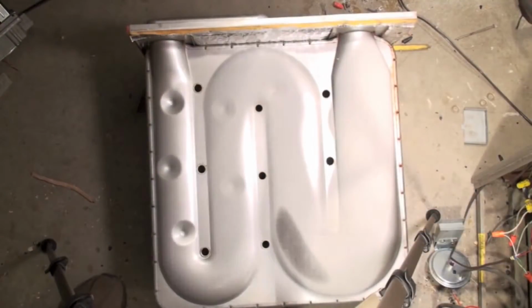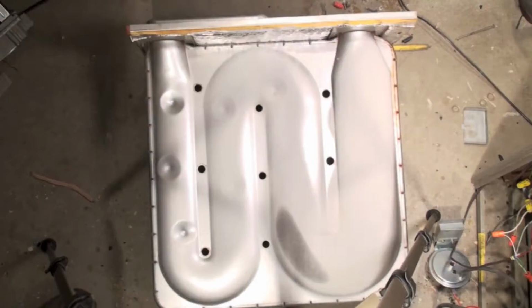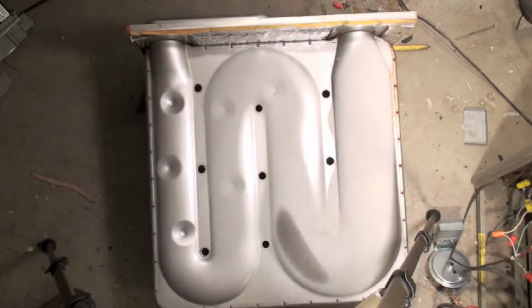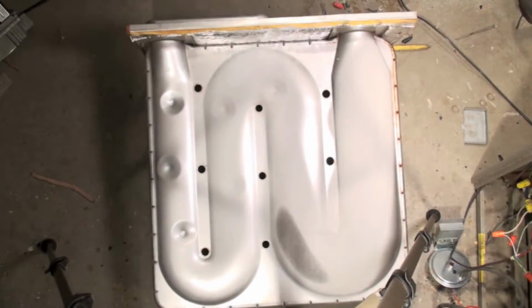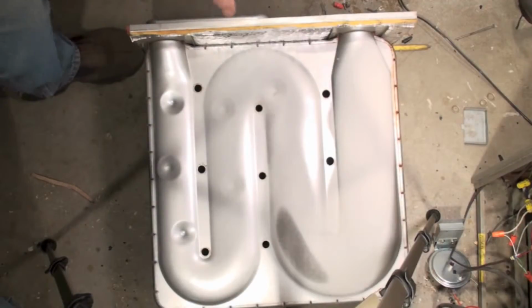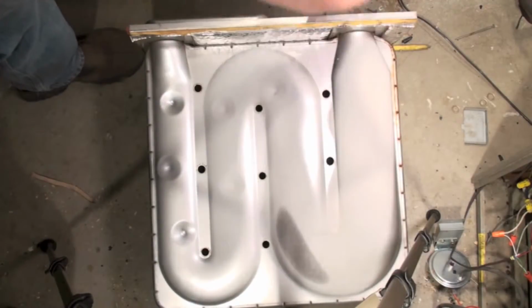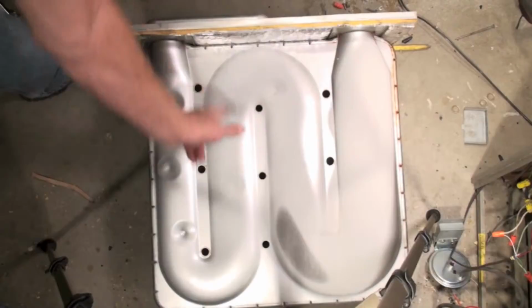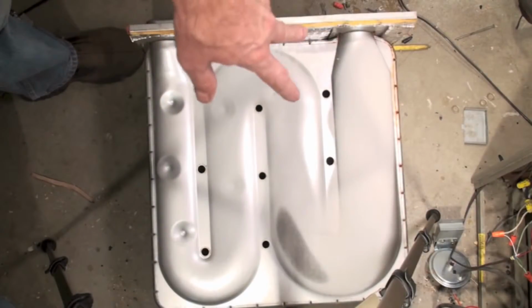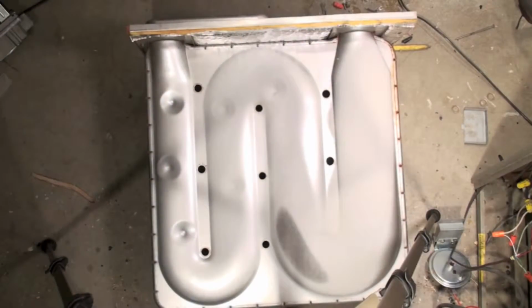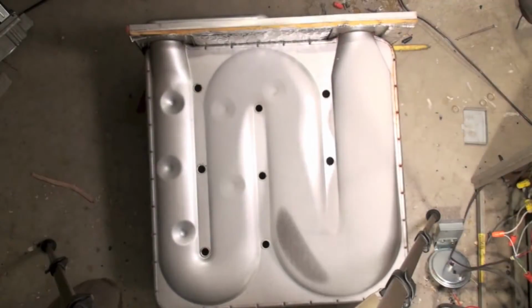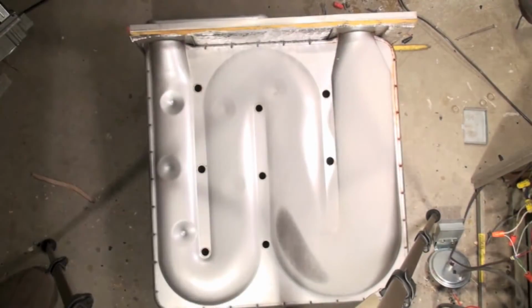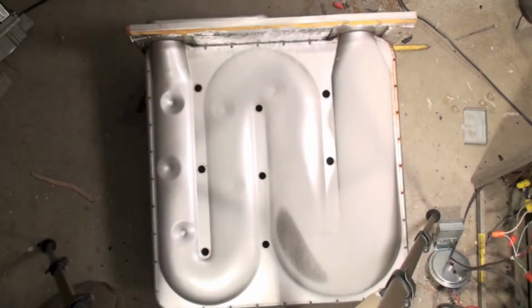Okay, here's our GMP furnace with the heat exchanger removed. If you look at this, you can see there's been no overheating. This is where the burners come in, and it goes up like this and out the vent. It wasn't overheated, so it was fired at about the correct firing rate. But I'm going to show you what happens to these heat exchangers and what part breaks.